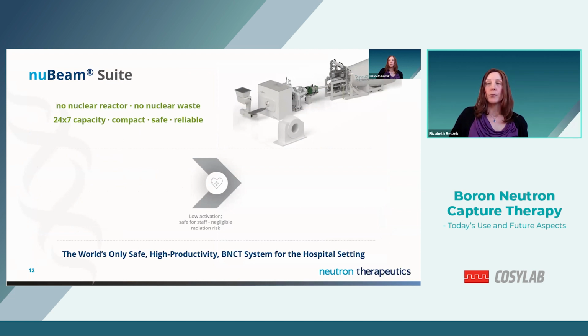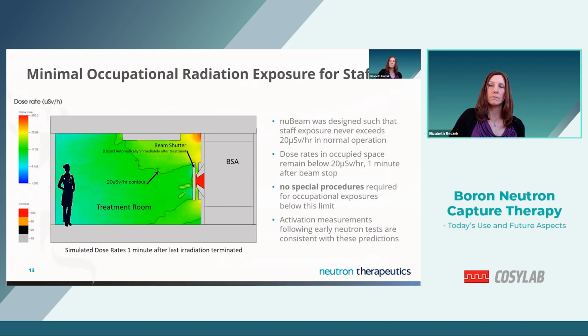The safety of the staff operating and maintaining the facility was of critical importance in the design of the nuBeam Suite to minimize disruption to workflows and maximize throughput. Our design target for staff exposure was 20 microsieverts per hour during normal operation. As shown here in the simulation, dose rates in the treatment room drop below this limit by 1 minute after beam stop, allowing the staff to enter the room almost immediately after treatment is complete, with no special procedures required. We've confirmed these projections in the Helsinki nuBeam treatment room using actual activation measurements following neutron beam testing runs.